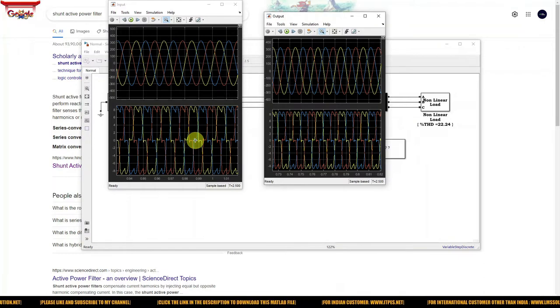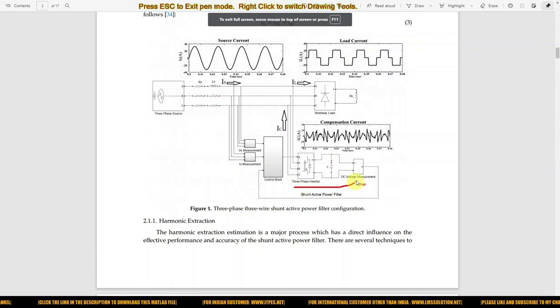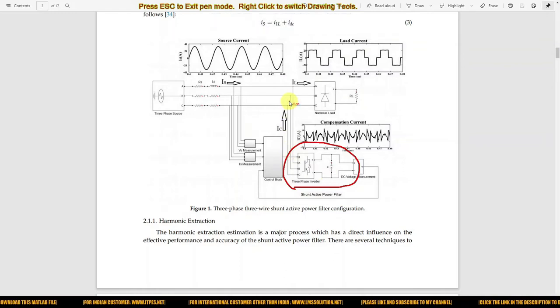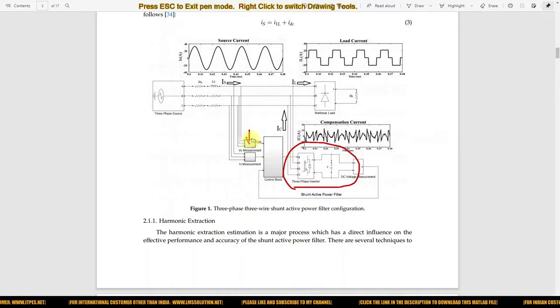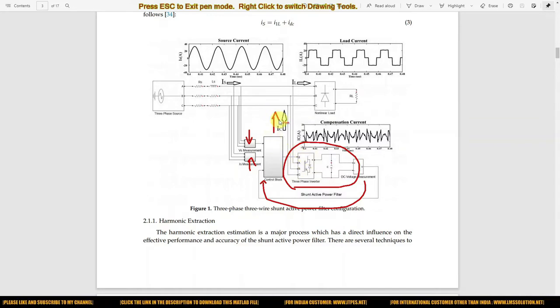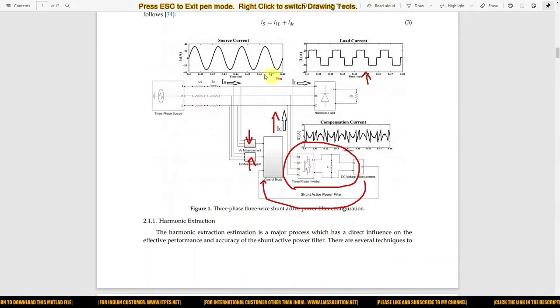For that purpose we use a shunt active filter. It consists of a three-phase inverter and a capacitor connected to the grid in parallel. Based on the grid voltage and current measurement and the DC link voltage of this capacitor, we generate pulses for the voltage source inverter, which injects a compensating current so that the source current remains sinusoidal even with a non-linear load.